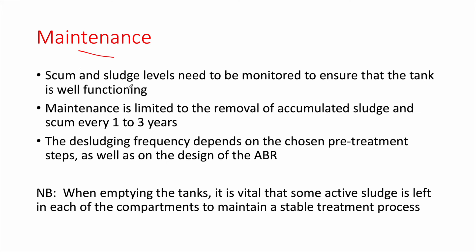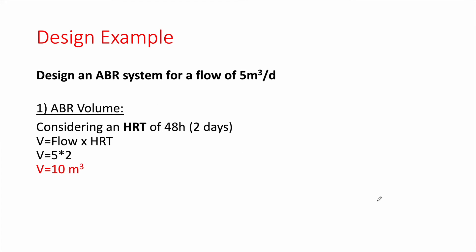Maintenance is similar to a septic tank — always check scum and sludge levels. It is limited to removal of accumulated sludge and scum, typically every one to three years. The desludging frequency depends on the chosen pre-treatment steps and ABR design. Crucially, when emptying the tanks, always leave some active sludge in each compartment, as removing all the sludge will highly affect removal rates and require another six to seven months for the sludge layer to reaccumulate.